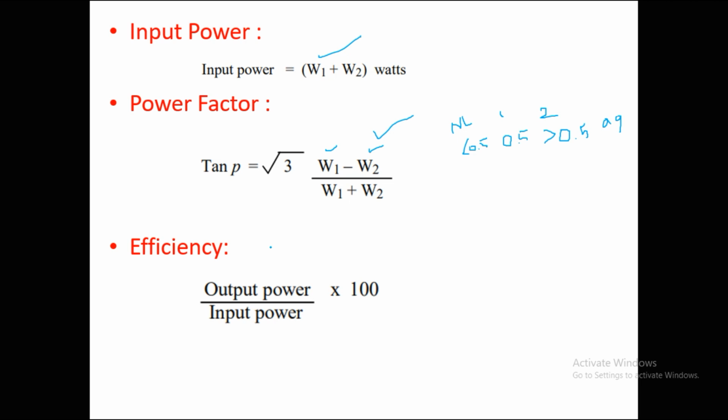We have to interchange the current coil terminals at no load, and at the time of giving a load step by step to the induction motor, again we have to re-interchange the current coil terminals. We have to keep that in mind while performing the load test. And remember, we have to operate the machine only at rated voltage and frequency. It means the voltmeter reading will never change. It will remain at a constant value.